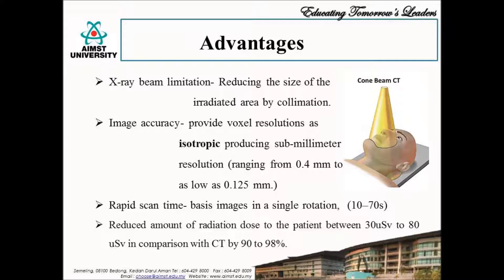Rapid scan time: because CBCT acquires all basis images in a single rotation, scan time is rapid, i.e. 10 to 70 seconds, and hence motion artifacts due to subject movement are reduced. Dose reduction: published reports indicate that the effective dose of radiation is significantly reduced, up to 98%, compared to conventional fan-beam computed tomography systems. This makes it a significant advantage over CT.